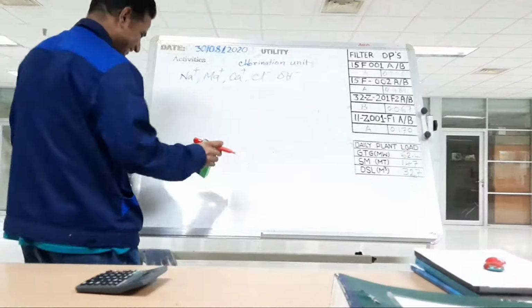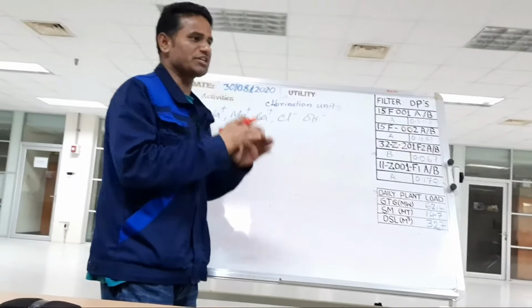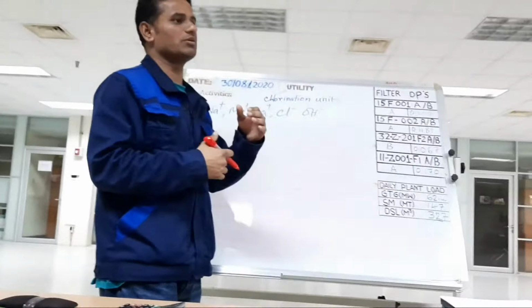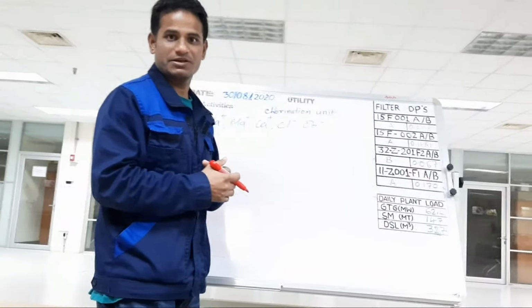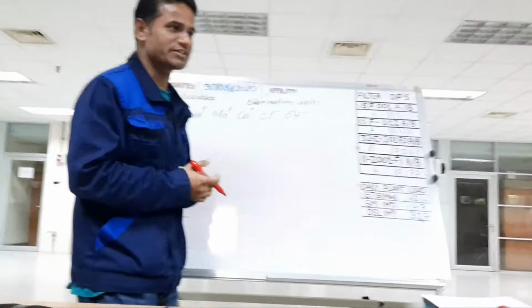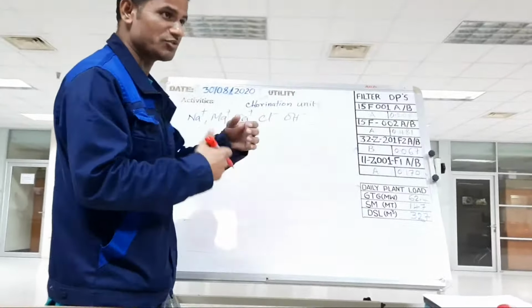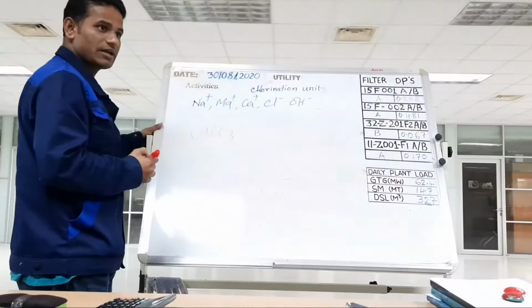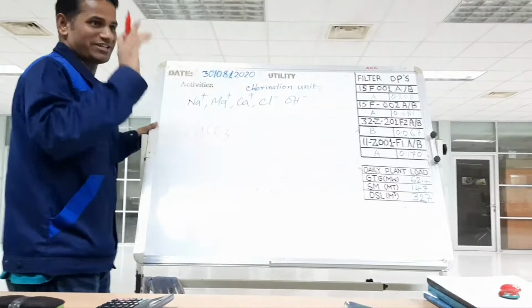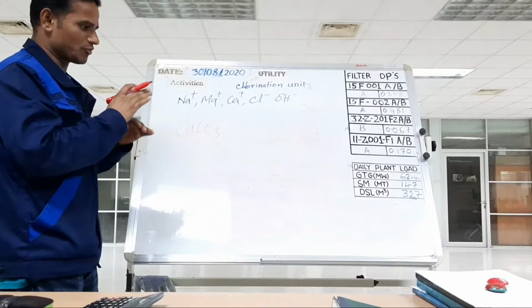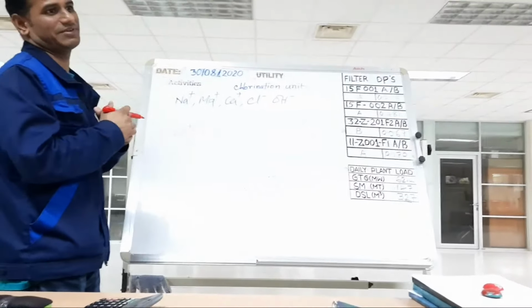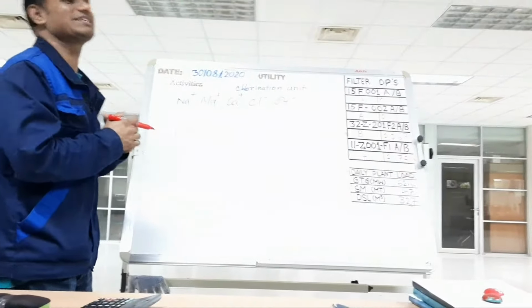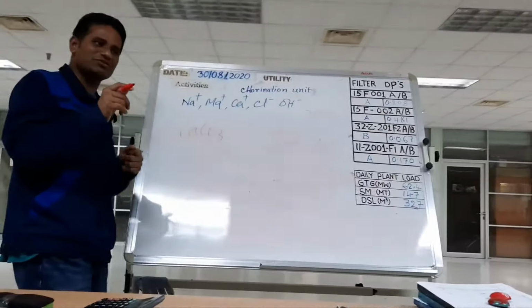As per the vendor, if the chlorination unit is stopped for 7 days, it needs acid cleaning. Why is acid cleaning needed? If it is running continuously and then stops, salts like calcium carbonate can deposit. Normally it is required once a year. Otherwise, if you stop for 7 or 15 days, or if performance is not good, you also need acid cleaning.